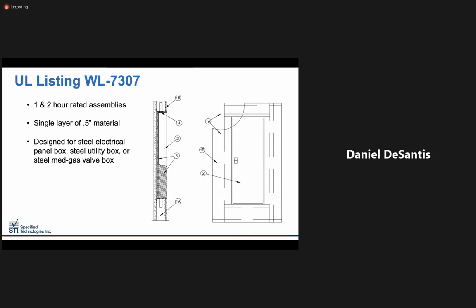Here we see STI's proprietary listing with UL, WL7307. This is for a recessed steel box, such as an electrical panel or med gas valve box. 1 and 2 hour F ratings are supported with this system with just a single layer of 1/2-inch EWRAP. This system only applies to boxes which are recessed in 1 or 2 hour rated gypsum wallboard assemblies and provides a lightweight solution for rating boxes that's easy to install and doesn't require any special tools to complete.